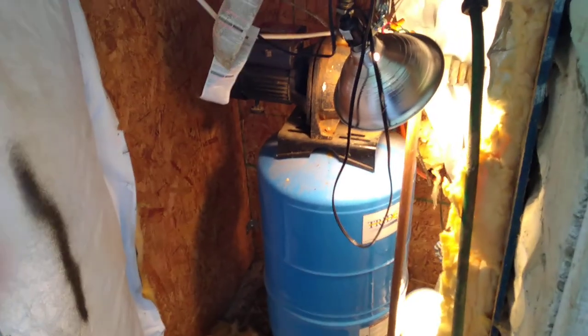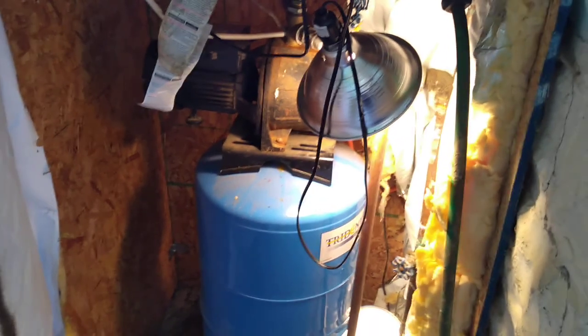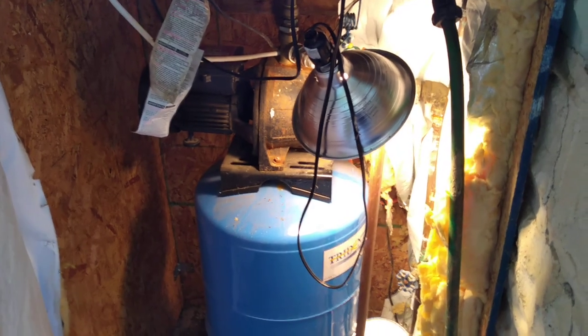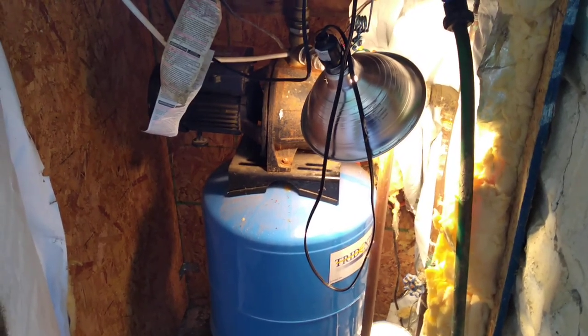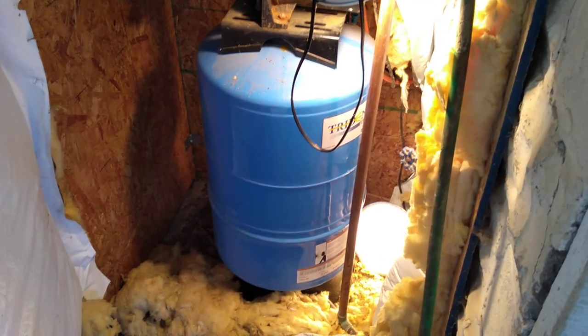In here I have a little area. There's a pump that sits on top of that pressure tank. It's just a shallow well, like a jet pump — it'll draw up to about 25 feet or so deep, so that's good enough for this application. And then that pressure tank keeps us with constant pressure down at the house.